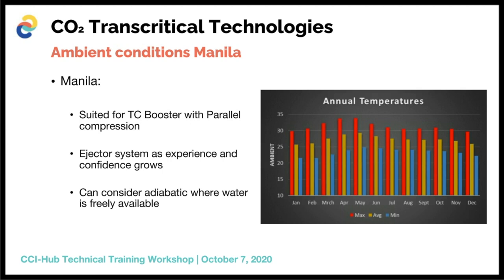Even worst-case high ambient conditions in the Philippines reach up to 34 degrees Celsius, still below 35 degrees, where parallel compression systems maintain better energy efficiency up to 37 degrees Celsius ambient. That's probably a guideline for what type of technology to introduce into the Philippine market. As more experience is gained, additional technologies like ejector systems can be introduced to further increase energy efficiency.